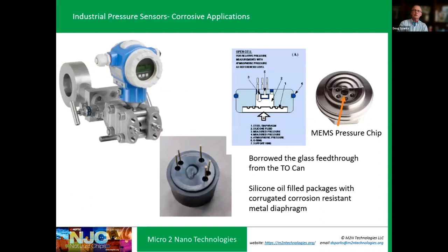In the industrial market, they ran with this idea, but instead of a Kovar TO can, they made these out of stainless steel—customized stainless steel Kovar cans with a pressure sensor inside, filled with oil, with a corrugated steel diaphragm. That way, the corrosive environment bends the flexible stainless or titanium corrugated diaphragm, transmitting pressure through the silicone oil and bending the silicon diaphragm.